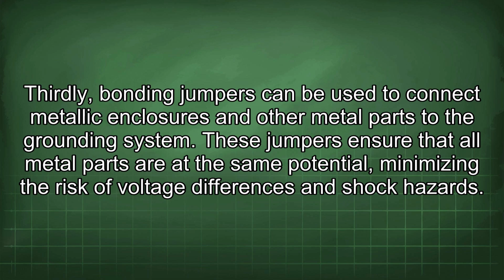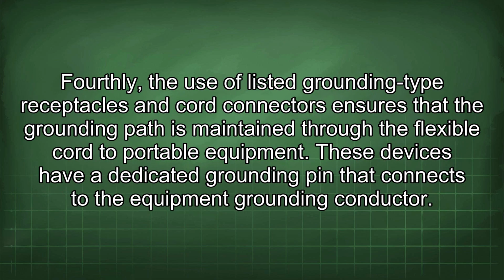Thirdly, bonding jumpers can be used to connect metallic enclosures and other metal parts to the grounding system. These jumpers ensure that all metal parts are at the same potential, minimizing the risk of voltage differences and shock hazards. Fourthly, the use of listed grounding type receptacles and cord connectors ensures that the grounding path is maintained through the flexible cord to portable equipment. These devices have a dedicated grounding pin that connects to the equipment grounding conductor.